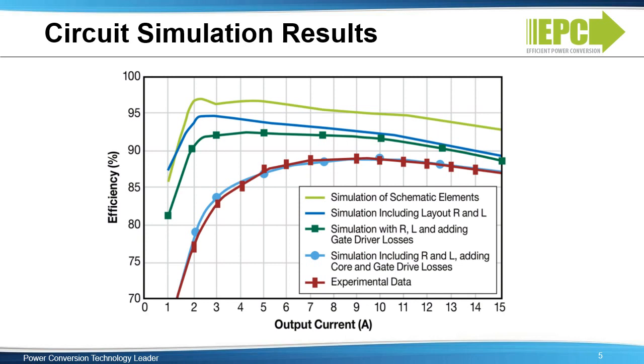To best illustrate this point, simulations with varying levels of complexity were made and the efficiency results on the vertical axis for each simulation were calculated as a function of load current on the horizontal axis and compared against an actual experimental result. The simplest simulation shown in light green only uses the device parameters to predict circuit performance. Adding layout parasitics reduces the predicted efficiency, as did adding losses from the gate drive circuitry. Adding the inductor core losses completes the picture and the simulation now closely matches the measured result. This circuit level simulation modeling is most useful to help correlate experimental measurements and gain a better understanding of device operation, since the measurements themselves are also limited in their scope and accuracy.